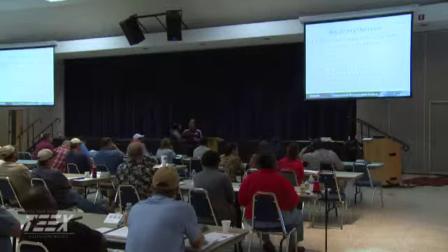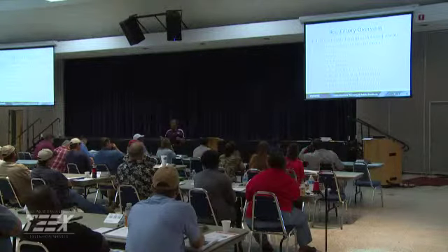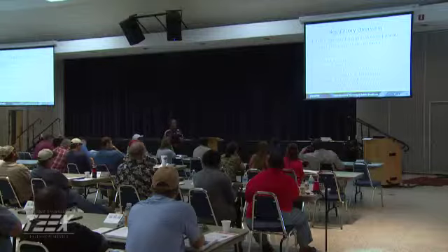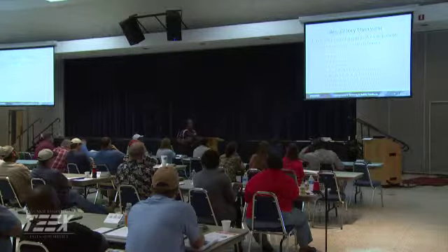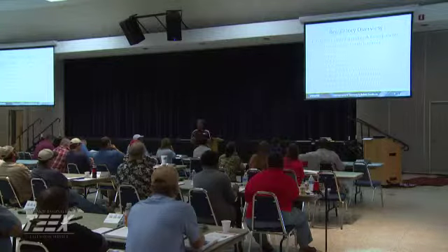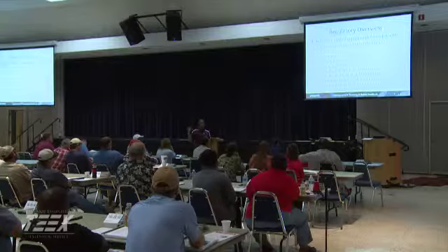So they will review your treatment scheme. They'll look at your distribution system and ask you for the results from the distribution system. What type of results are we looking at there? Our bacteriological sampling, chlorine residuals, something else. How many of you all do total trihalomethanes and haloacetic acid? You're going to have to pull those records for review also.